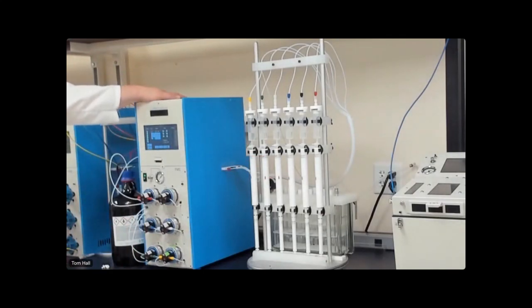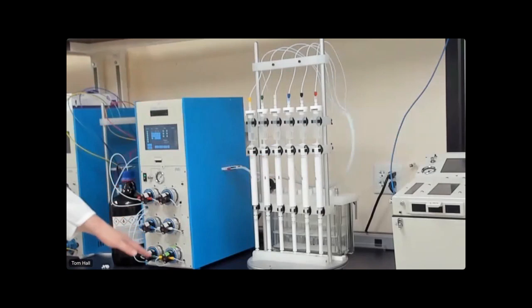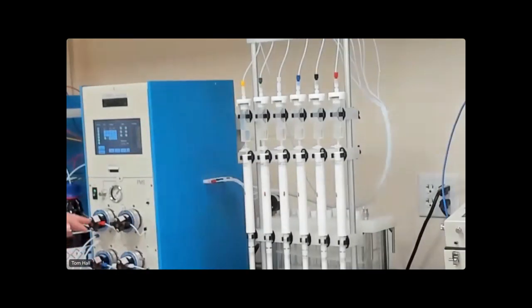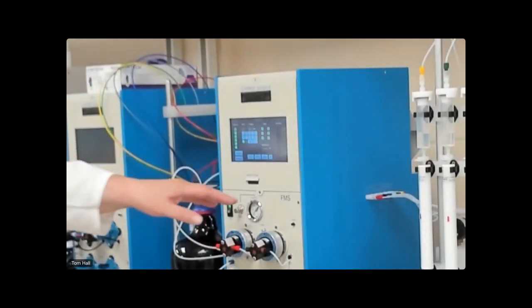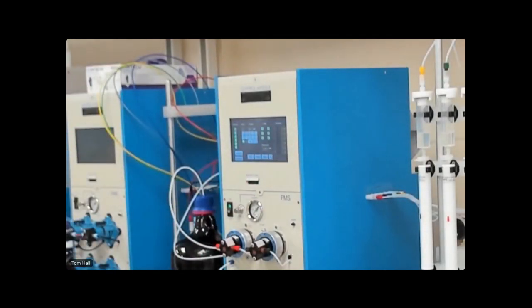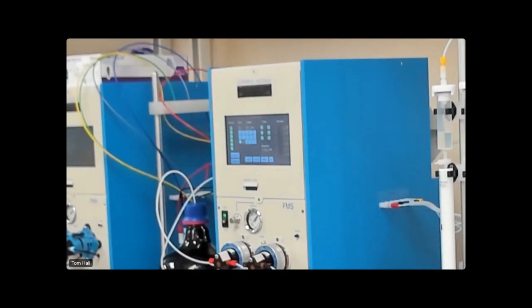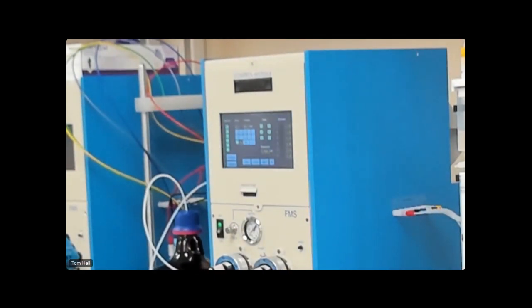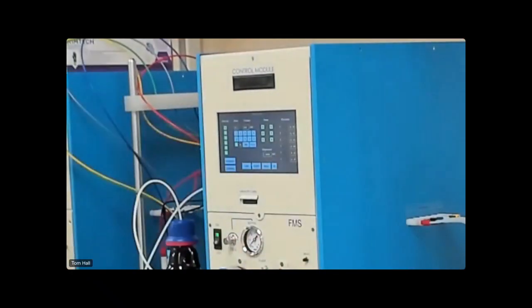This is the multi-pump. Tom already mentioned you can run 6 samples at a time. You have 6 pump heads here. They're color-coded, red and black, etc. We have the on-off switch. We have a nitrogen feature here, which we typically use at a low setting, about 5 psi, pounds per square inch, or about 1/20th of an atmosphere, to blow the hexane during the first step of the process down onto the column after the loading of the hexane is done.